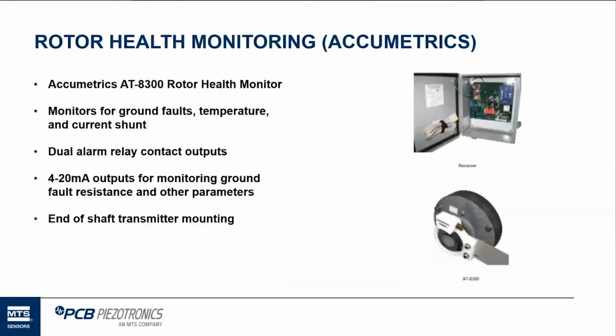Also at ACCUMETRICS is our rotor health monitor, again, one of the many systems that ACCUMETRICS provides. So the AT8300 is looking at rotor health. It's looking at some ground faults, temperature, and current shunts. It's got some relay outputs that can be used for alarms, maybe an alert and a danger alarm, turn on a light or ring a bell, whatever. Some of these have been implemented in some smaller units to provide feedback to the plant to tell it that there's an issue. It has 4 to 20 outputs for going into a PLC.